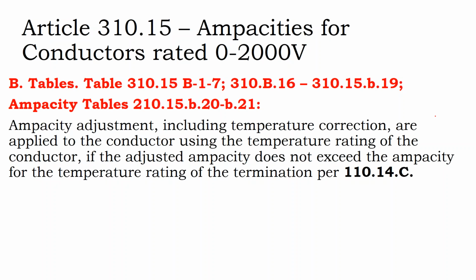So ampacity adjustments, including temperature correction, are applied to the conductor using the temperature rating of the conductor if the adjusted ampacity does not exceed the ampacity for the temperature rating of the termination. And so if your conductor is 90C, you can do a 90C calculation, but if the terminal is rated for 75C, you may have to redo your calculations at 75C.